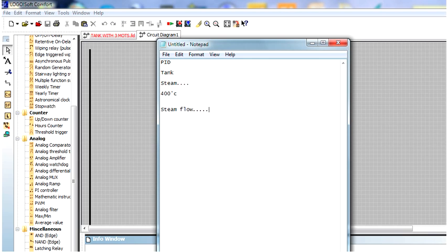So how will you control the steam flow? If I use a PID controller, we can do it very easily. We must use a flow control valve — that is an actuator valve — and this valve will be controlled with a 4 to 20 mA signal or a 0 to 10 V signal.